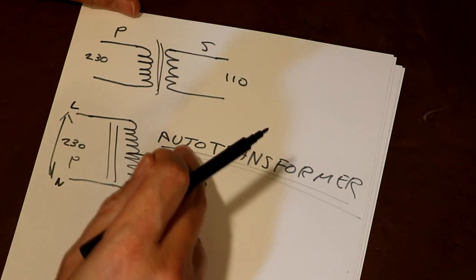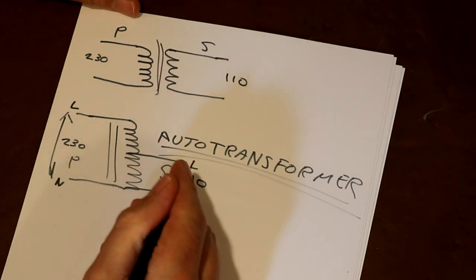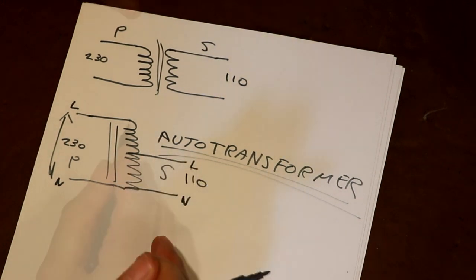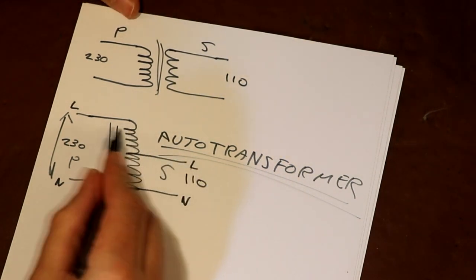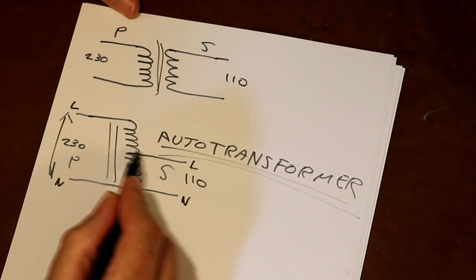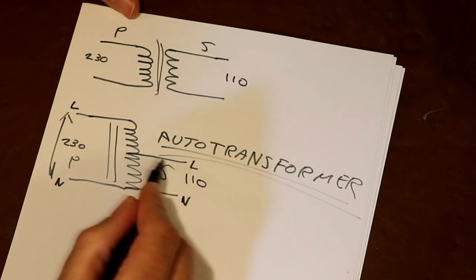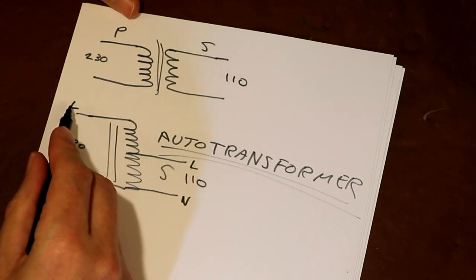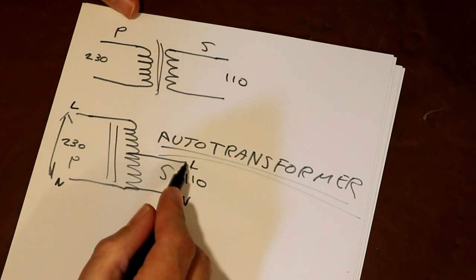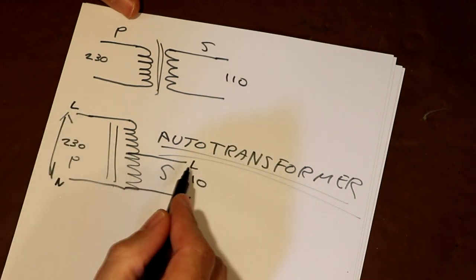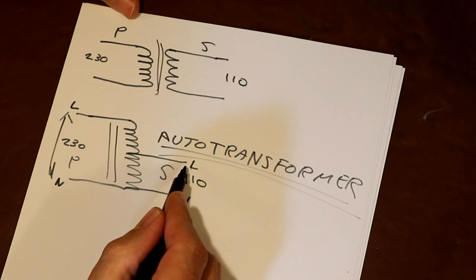If you were to touch this live wire here, you would get a belt. You could get certain situations where maybe you get some shorted windings in here, and again you could more easily directly connect this live input to the output, so it's more likely to get a failure, and if we do get a failure, the lack of isolation means it's less safe.